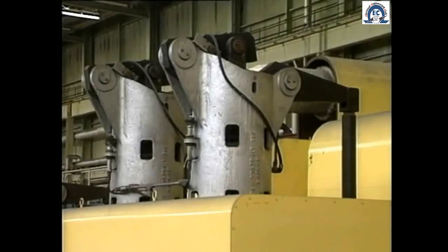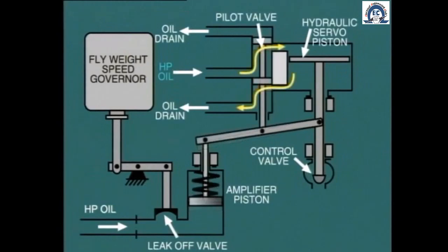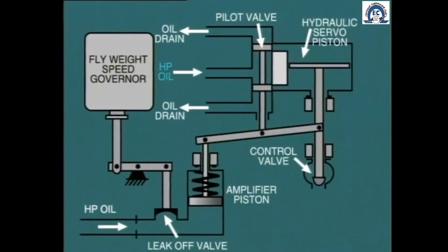On large turbines with multiple control valves, a considerable amount of power is required from the power cylinder. In this case, it's usual to employ a double-relay type of pilot valve. In this arrangement, we have high-pressure oil above and below the piston. When the position of the governor spindle changes — say for an increase in speed — the pilot valve lifts and allows high-pressure oil to flow into the space above the power piston. At the same time, the pilot valve exposes the space below the piston to the oil drain and returns the oil to the tank. The high-pressure oil above the piston pushes it downward and consequently moves the control valve in the closed direction. At the same time, it also moves the reset lever to bring the pilot valve back to neutral position, preventing further movement of the control valve.